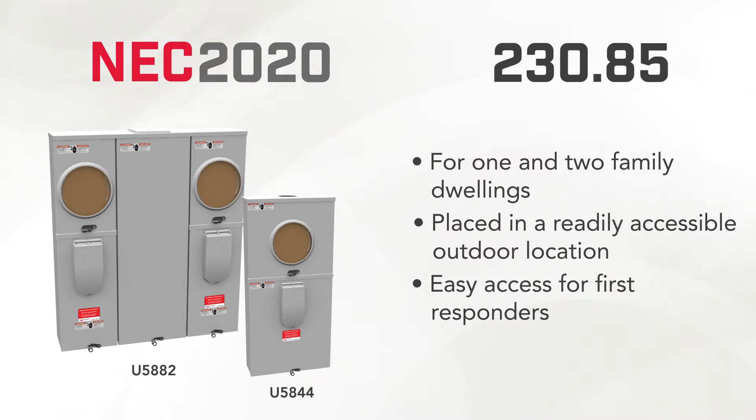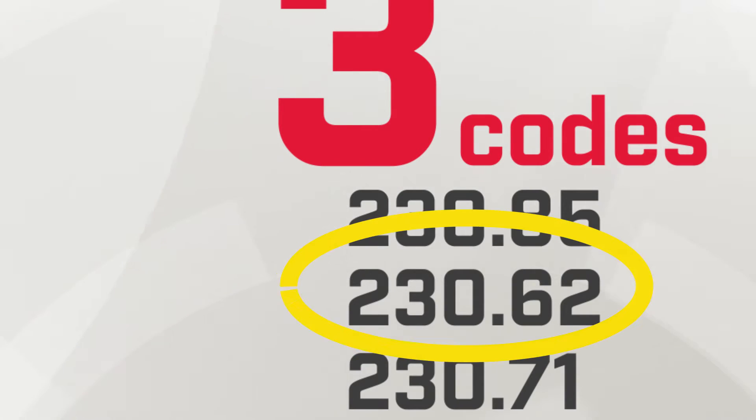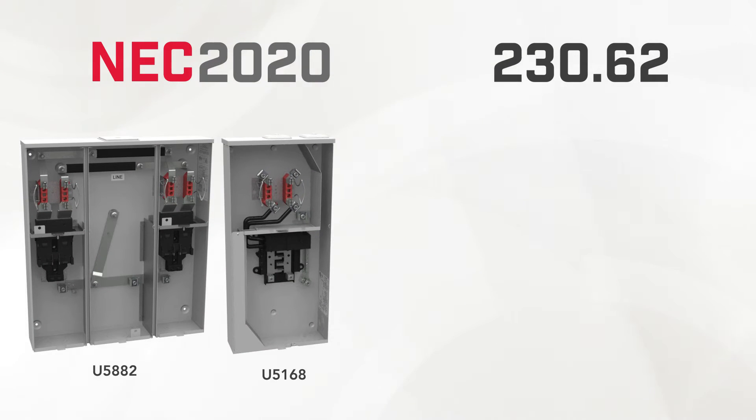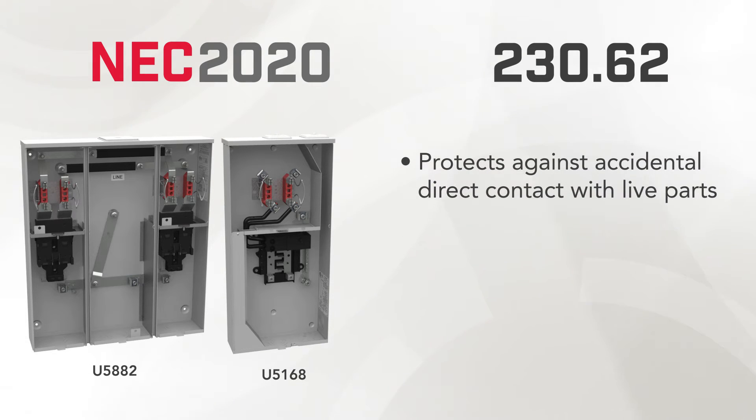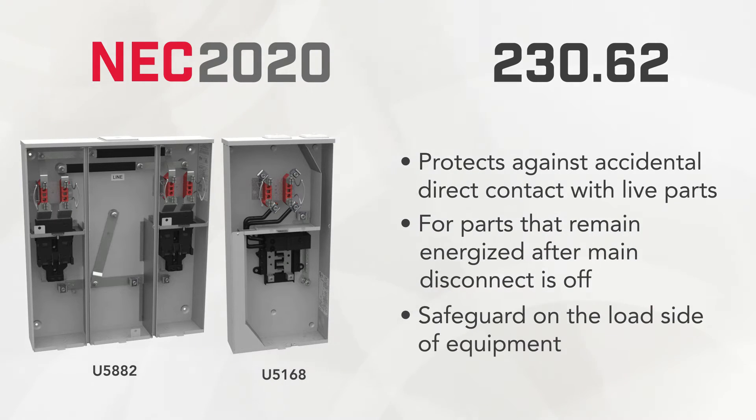Milbank offers many meter main products to help your customers meet this code requirement. Next, let's talk about Code Section 230.62. This code requires service equipment to have energized parts enclosed or guarded to protect against accidental direct contact with live parts. This requirement is for parts that would still be energized once a main disconnect is in the off position.